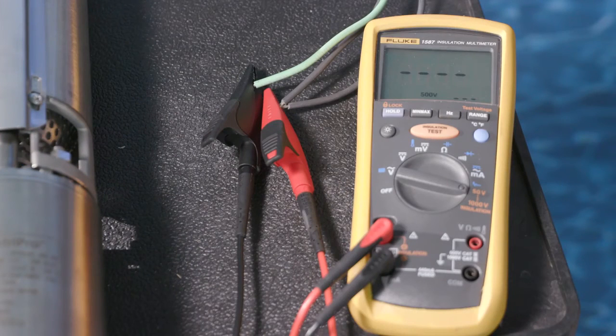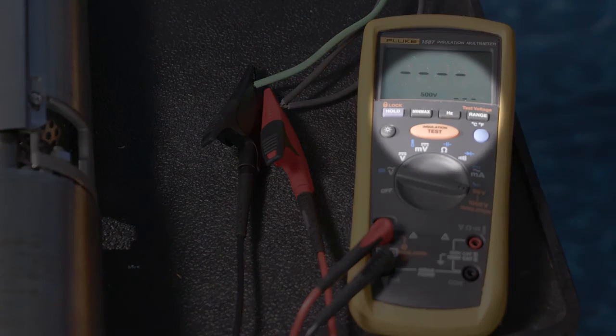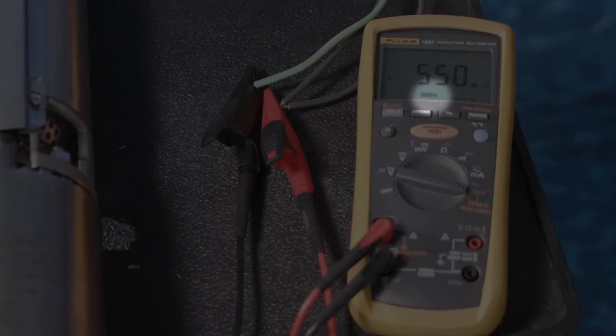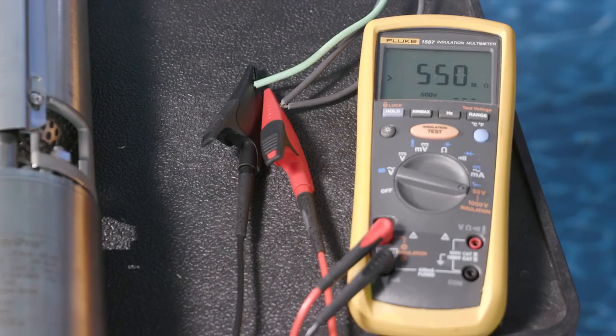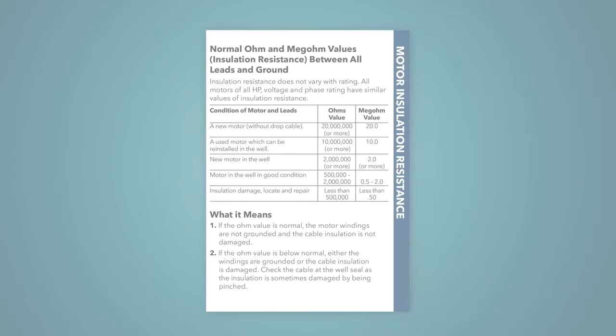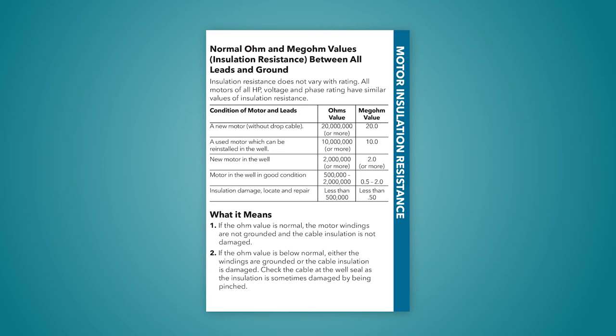To measure line-to-ground resistance with a digital insulation resistance meter, or megger, again, ensure there is no power to the motor. First, set the appropriate DC voltage on your meter. Use 500 volts DC for our Goulds Water Technology products. Then, measure the resistance between each of the leads to ground. Compare the actual measurements to the normal ohm and megohm values chart in the Pocket Service Manual and determine the meaning of the results.